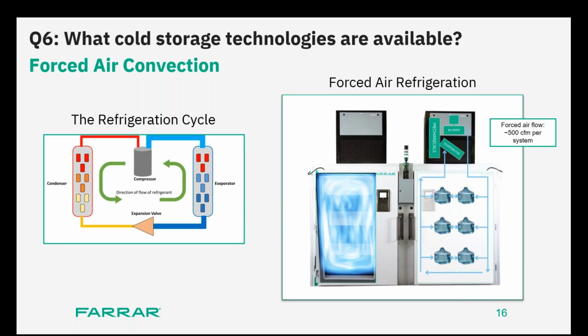In this case, you don't have to worry about it because as you're running the auto defrost and melting that ice, you could still leave your samples inside the chamber and they maintain integrity. So that's the third aspect, the auto defrost. If I were to sum things up, once again, forced air convection and cold wall technology are not actually having this headbutting contest.